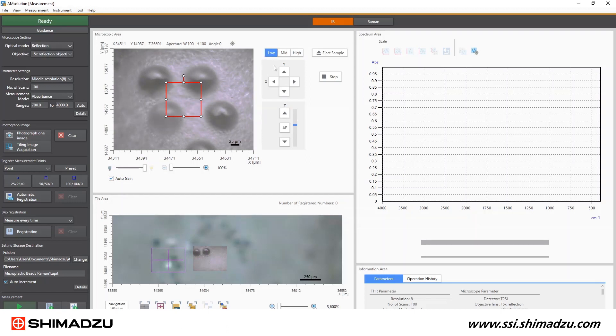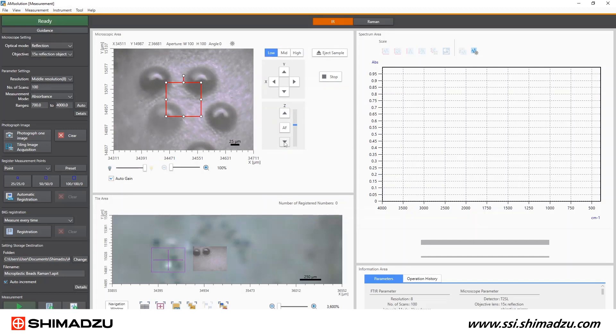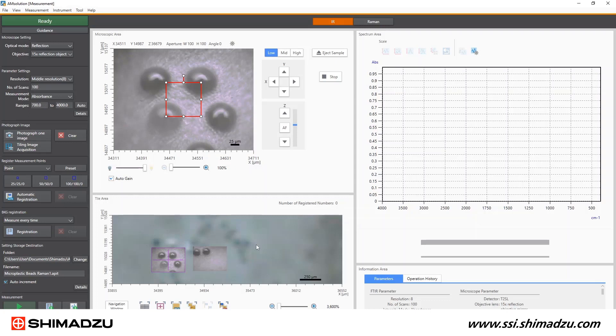Here's a nice example. It's a good idea to do some fine adjusting in the Z height to really bring the focus to the top of the sample and optimize the IR beam path. This looks nice. So I'll click photograph one image again to capture the magnified image at that location. And notice how this image is overlaid on the wide field image.